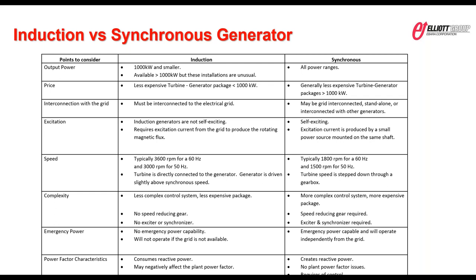Or an induction generator, it's essentially an induction motor. It doesn't have an exciter, so it takes its voltage and frequency from the grid that it's connected with. So if you lose power, you lose the grid, that generator is going to have to shut down unless there's something else to regulate its frequency and voltage. There's also a rule of thumb when you're talking about induction generators. Roughly, if that generator is going to be about a third or more of your total plant load, then an induction generator is not the way to go. You need other things like capacitor banks to help offset that reactive power. So if it's going to be a larger unit that makes up a majority of your plant load or your facility's load, then you should go with synchronous.